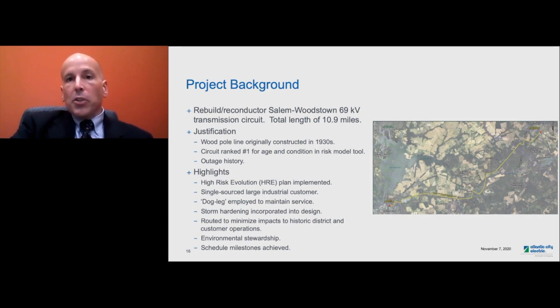Periodic inspections of the energized transmission circuits were completed, generally via helicopter flight patrols, to confirm there were no new issues. This slide references a dog leg where a line was installed from the transmission circuit to the industrial customer served directly from the transmission line. This dog leg was a line extension designed and constructed prior to the rebuild.